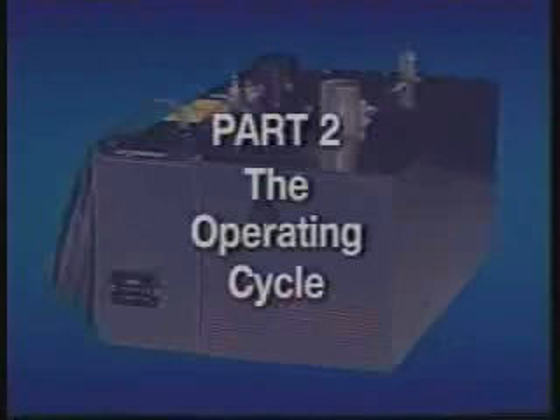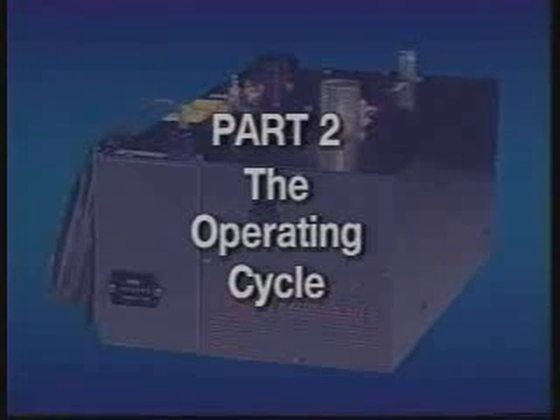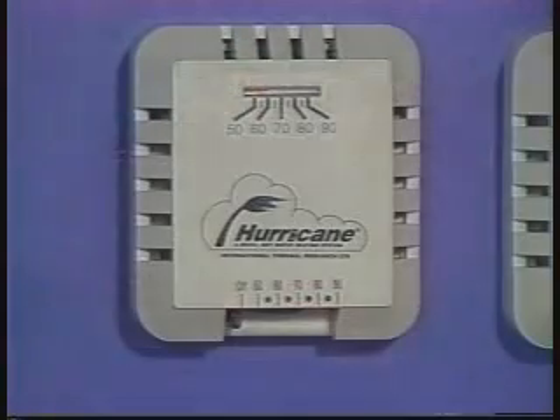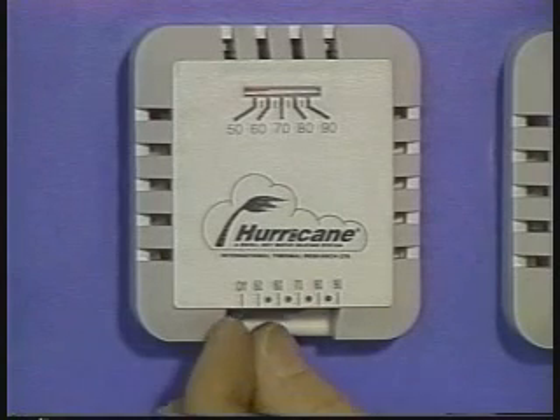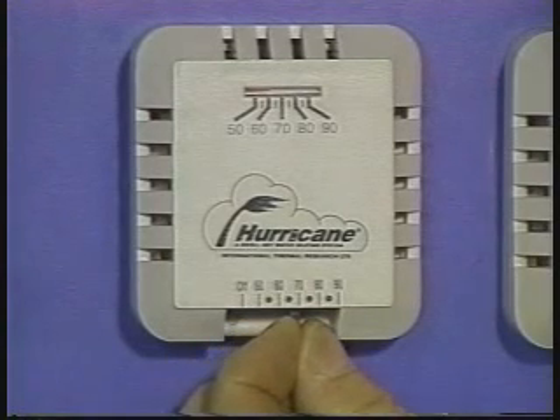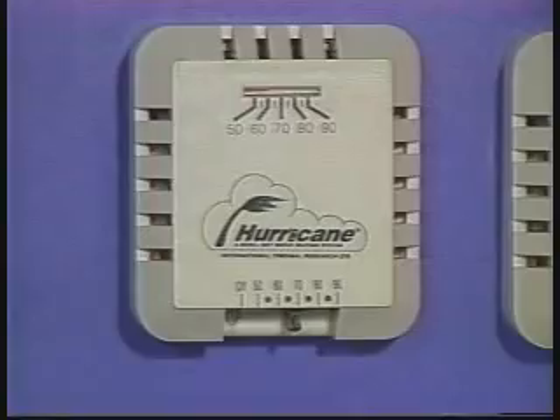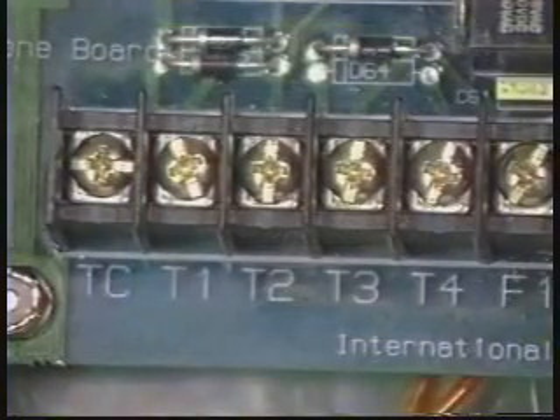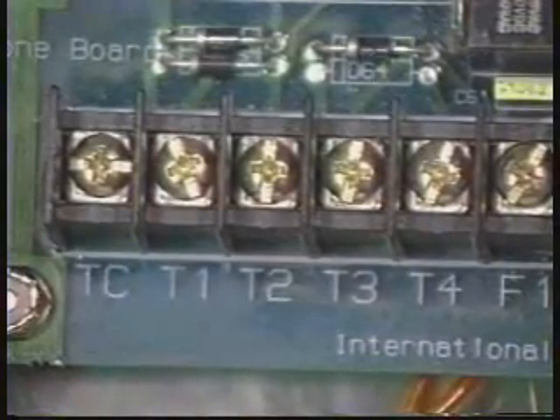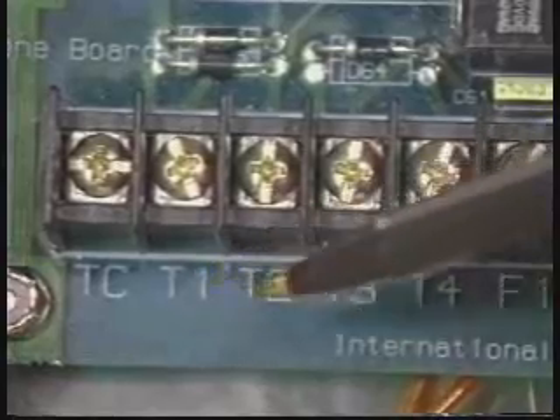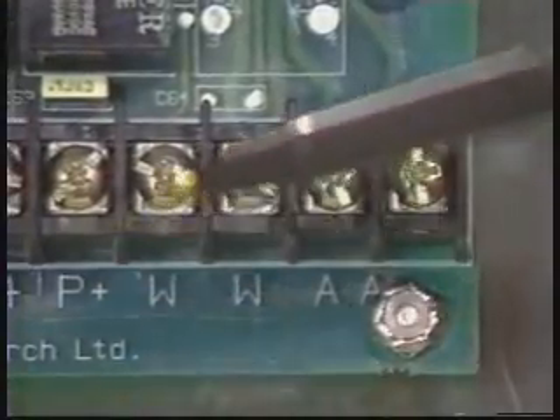In this section, we will examine the operating cycle of the furnace, component by component, paying particular attention to the sounds and the appearance of the furnace as it starts and runs. The furnace run cycle begins with a call for heat from a thermostat or operating device. There are two circuits on the furnace zone board that can cause the furnace to run. These are circuits T1 through T4 and the WW circuit.